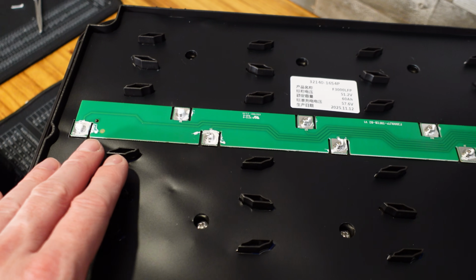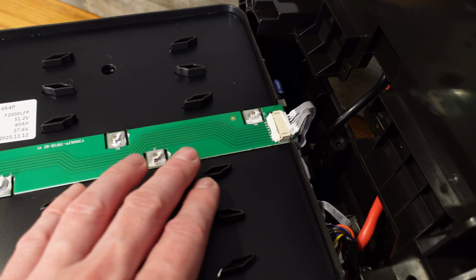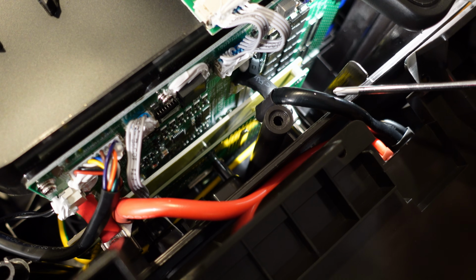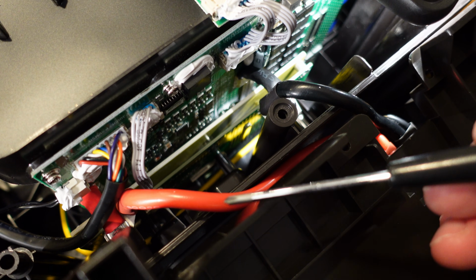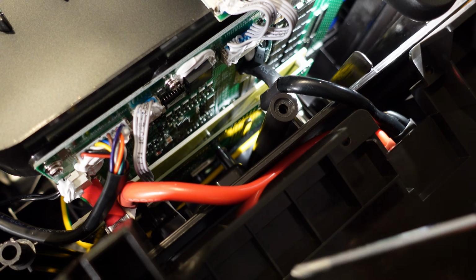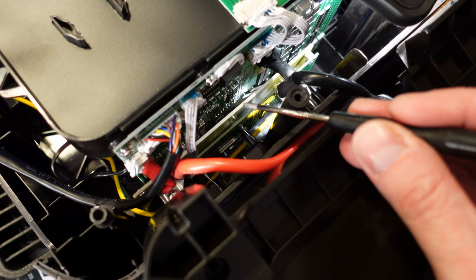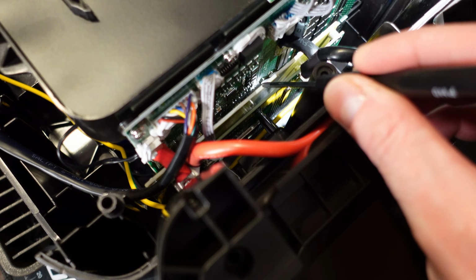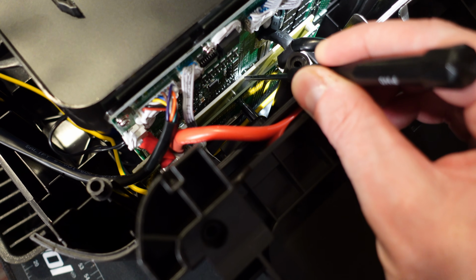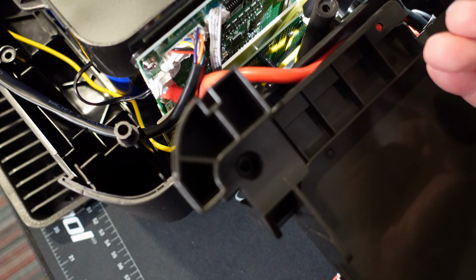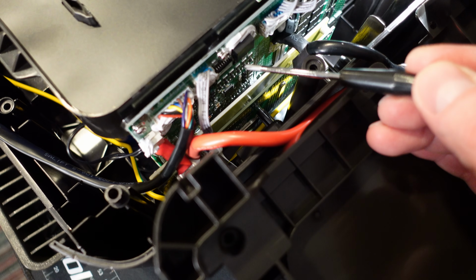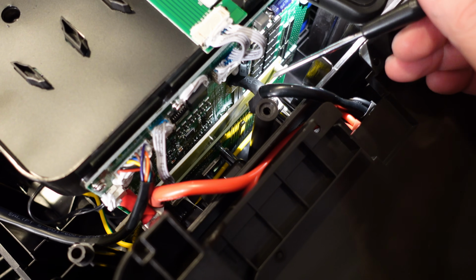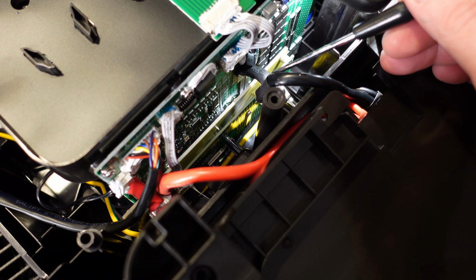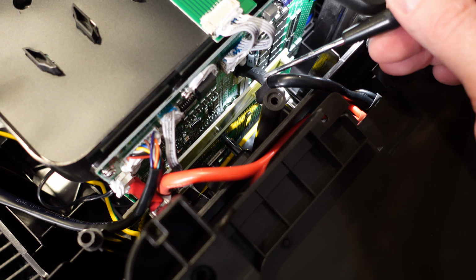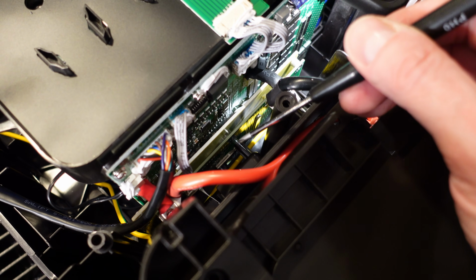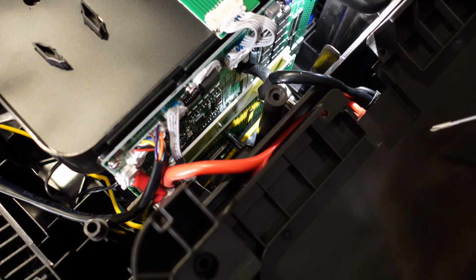This PCB is collecting the balance leads and taking them back to the central point here. So of particular interest here is how they're handling that battery expansion port and whether or not that goes through the BMS. So this board located right here is the board that the XT120 is connected to, and this board right here is our BMS. So this connection point is combining the battery power off of the BMS with the battery power from the XT120 and then sending it to the inverter.